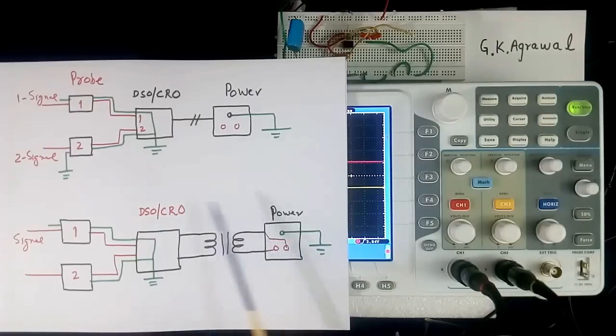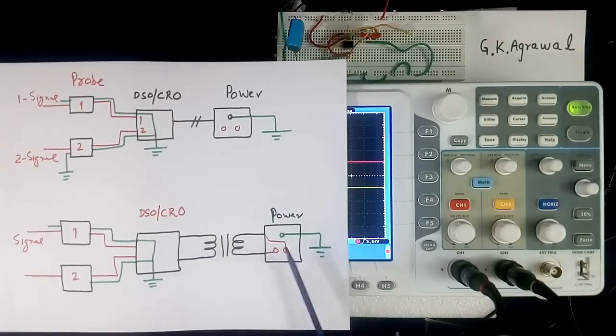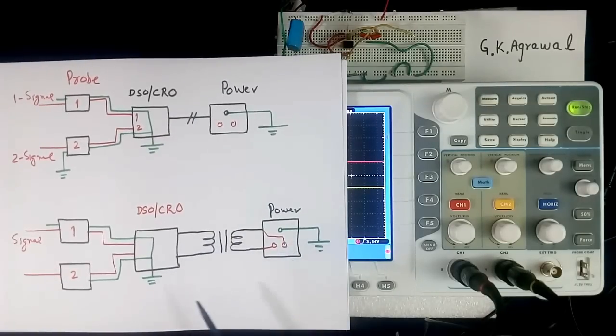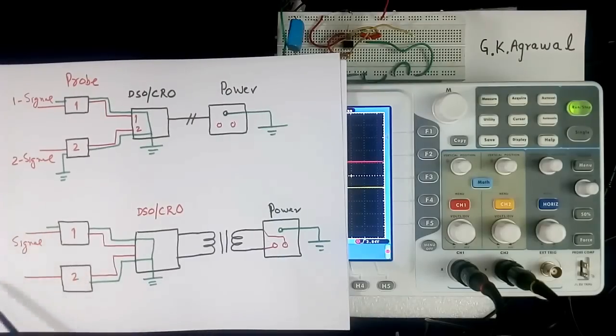This is much safer way of using CRO. Please connect a transformer between CRO and power. Then this point don't connect to earth. It can be kept floating. And this common can be connected to signal common, wherever required. I have shown here. But this point is actually earthing of incoming signal.